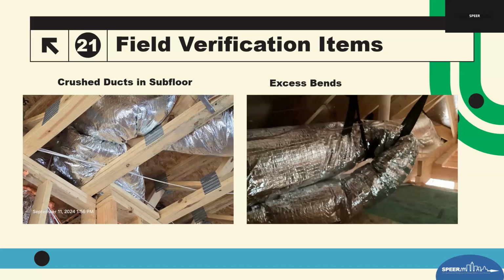And so this that we see on the left was actually done on site. I was part of this. We actually had it tested, and we were able to prove at the end that we were losing anywhere from 30 to 50% of the airflow, about 30% on the supply side and 50% on the return side. If you were part of that webinar, you've already seen the results from that. This is why it comes from things like this. And of course, excessive bends.